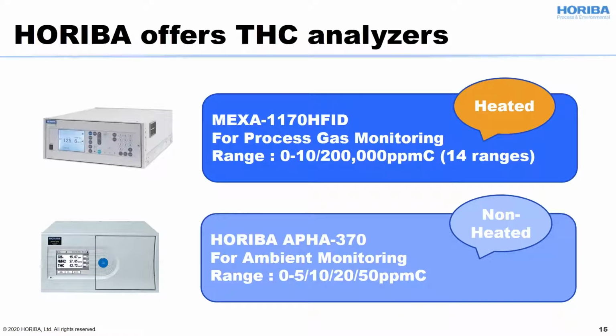HORIBA offers two types of total hydrocarbon analyzers, as the slide shows here. MEXA-1170HFID is for process gas monitoring. Inside of this analyzer is heated because if your application contains high molecular weight hydrocarbons, you might lose those during the sampling. But by heating all of the sample flow line, you can prevent the loss of those hydrocarbons. Usually, MEXA-1170HFID is used for process gas monitoring. As you can see, it covers a wide range from 10 ppmC to 200,000 ppmC, and you can set up 14 ranges within this wide range.